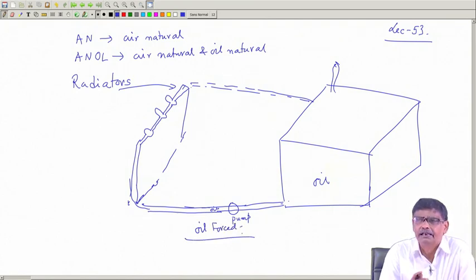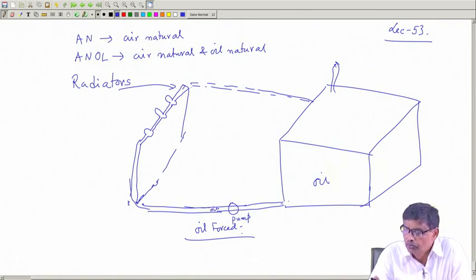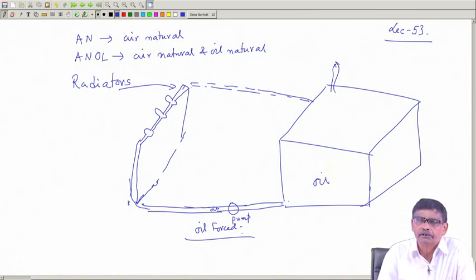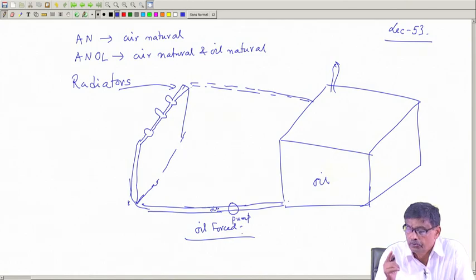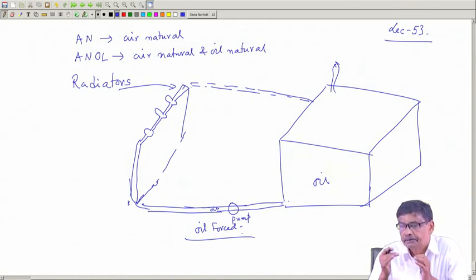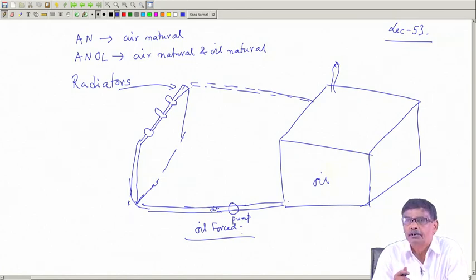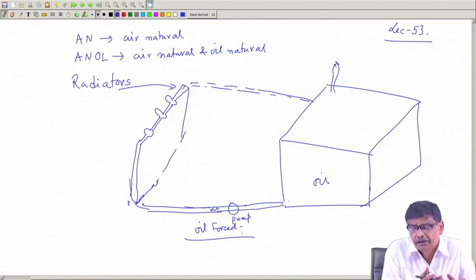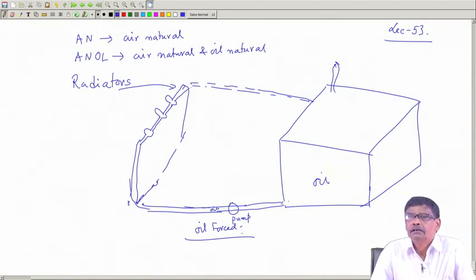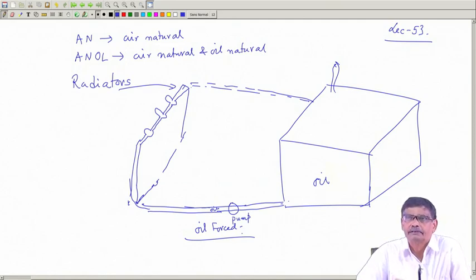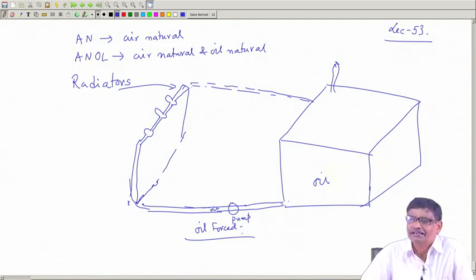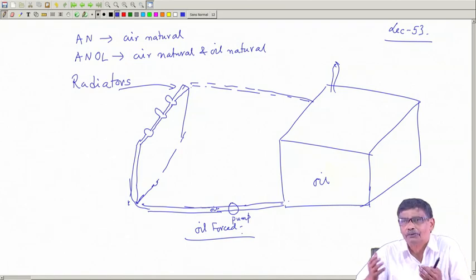So, the idea is very clear. If you want to use very large transformers, you must do extra to cool the transformer, so that the temperature rise is within the limit, because whether it is a very small or a large transformer, the value of Bmax, the magnetic loading, is approximately the same, maybe 1.2 Weber per meter square.